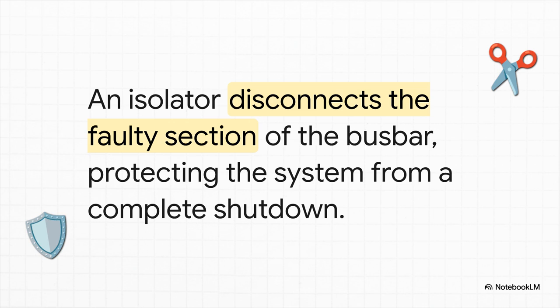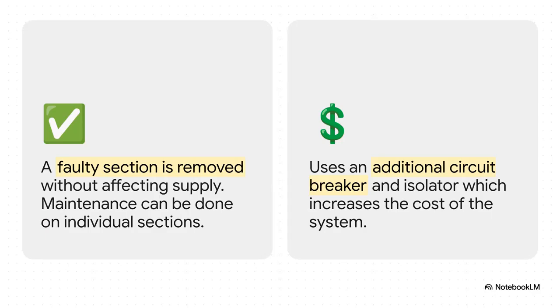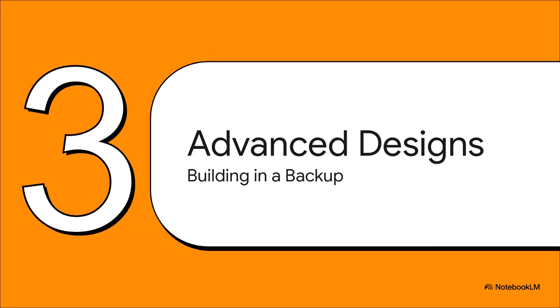Brilliant, right? The main takeaway here is that you gain a huge amount of reliability. You can even do maintenance on one section without shutting everything down, which is a big deal. But there's always a trade-off: you've added more equipment, that extra circuit breaker and isolators, and that's going to increase the cost. But for major power stations, for those really critical substations, medium reliability just isn't going to cut it.